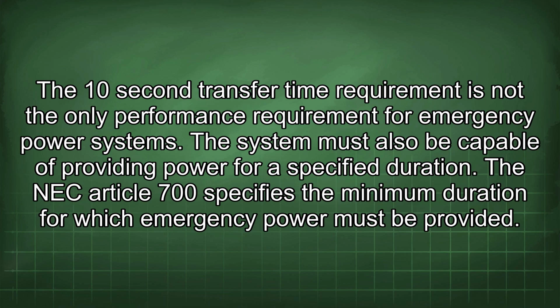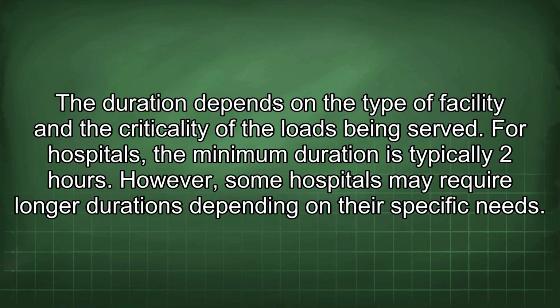The 10-second transfer time requirement is not the only performance requirement for emergency power systems. The system must also be capable of providing power for a specified duration. The NEC Article 700 specifies the minimum duration for which emergency power must be provided. The duration depends on the type of facility and the criticality of the loads being served. For hospitals, the minimum duration is typically 2 hours. However, some hospitals may require longer durations depending on their specific needs.